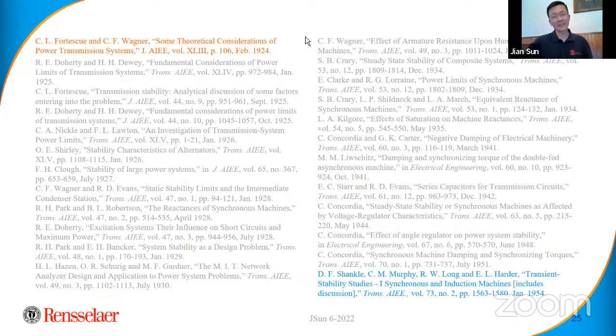Under certain conditions, the negative damping becomes dominant, and so you have an unstable resonance that manifests itself into a growing harmonic, and that will shut down the system. It's a hidden danger, actually, and it can be mistaken as a power quality problem, but fundamentally it's a stability problem. So you cannot just filter it out, it's not a current source, it's being created. You have to modify the dynamics, modify the impedance to damp the resonance.